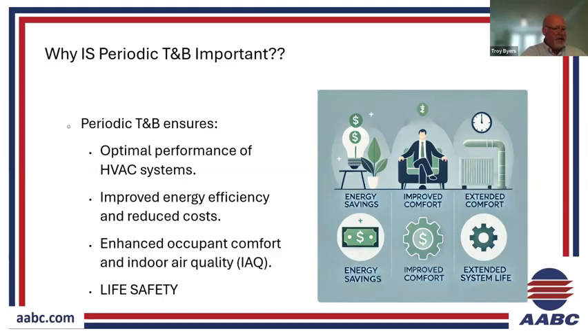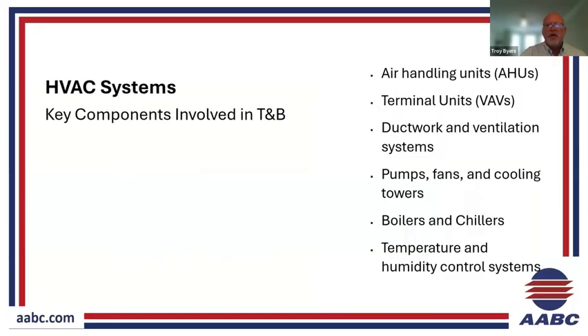So, all right, with that, we'll go ahead and move through. Okay, so typical key components that are involved in the testing and balancing of HVAC systems. We see air handling units as the source of conditioned air, and then going out into terminal units for distribution, ductwork, ventilation systems, pumps, fans, cooling towers. These are some of your major pieces of equipment, with boilers and chillers, and then the control systems themselves to maintain our temperature and humidity and sequencing of our systems.